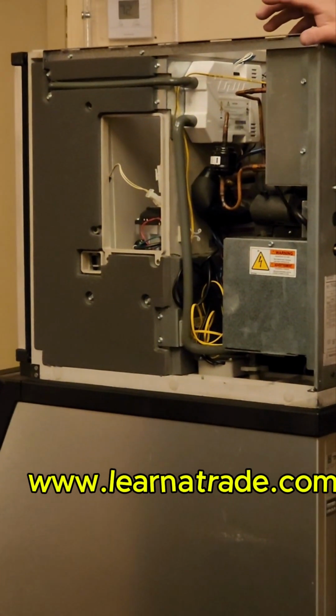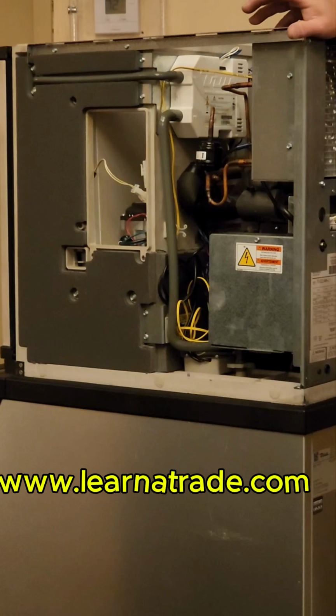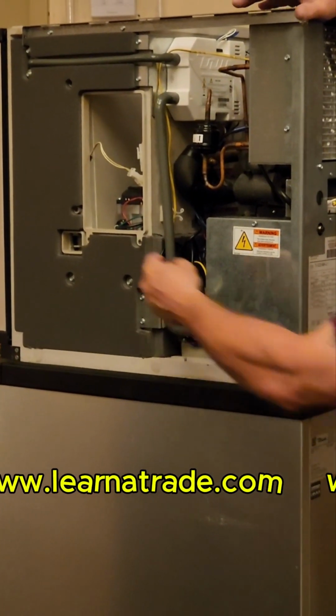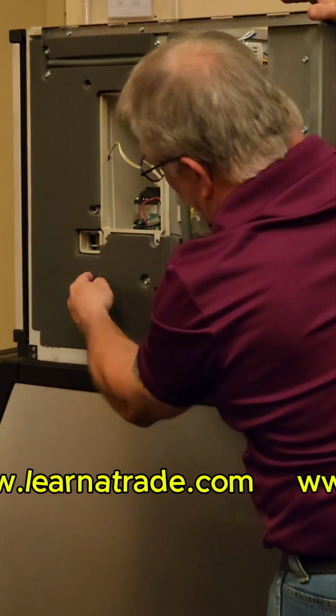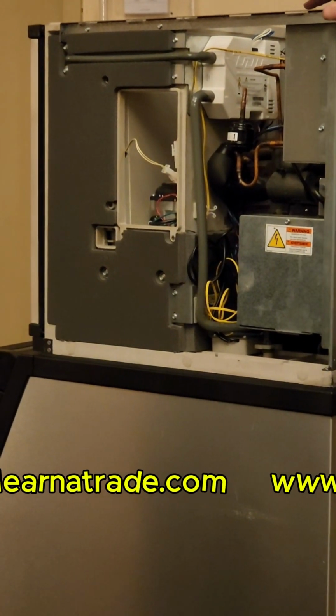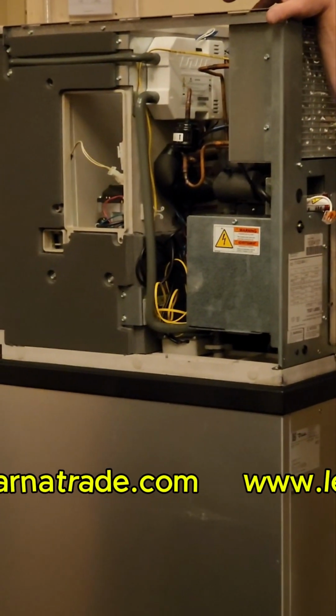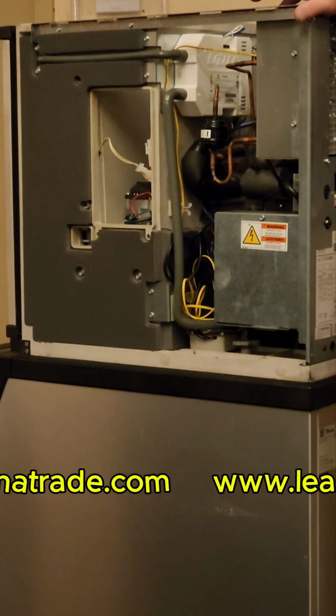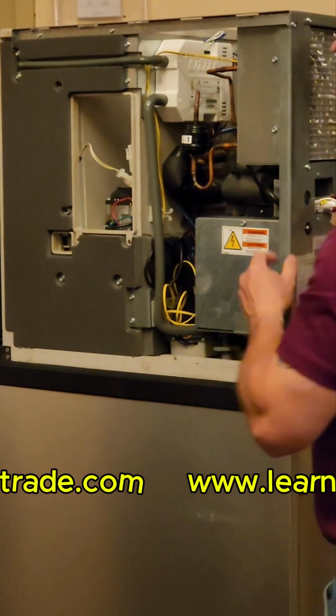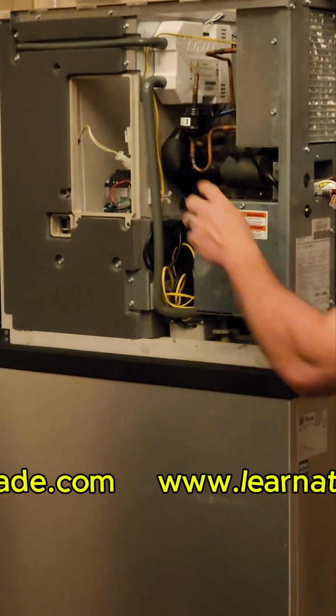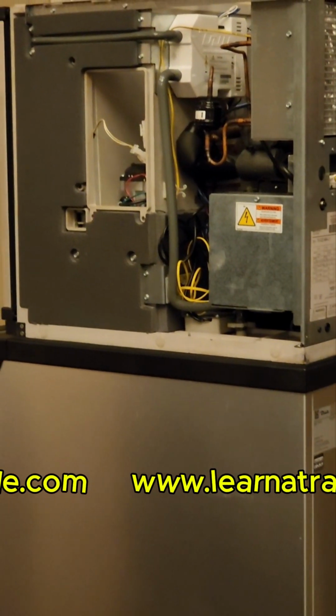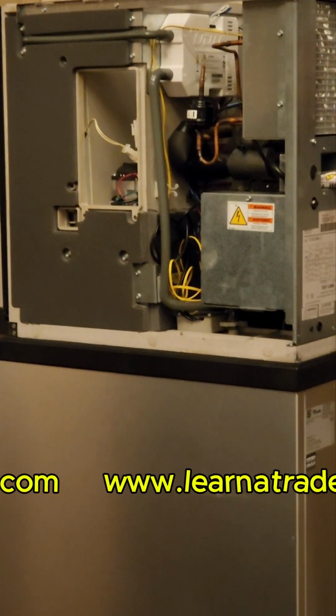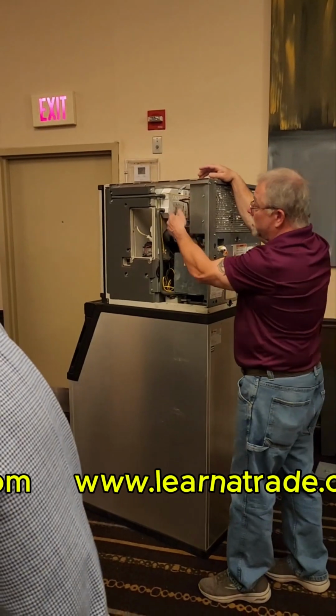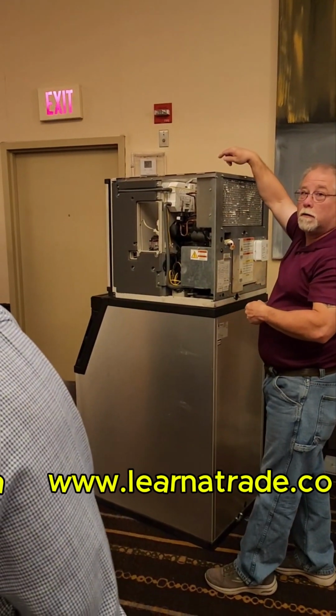Do you have a question? Yeah, if it comes down to it, is it possible to change the evaporator? Well, come on, oh golly, yeah. One, two, three screws on that side, three screws on the other side. Pierce the valve into your refrigerant line, dump the charge, cut it out—I'll show you on the other side. Cut out your liquid line dryer, and of course anytime you open the system, change your liquid line dryer. But it's 3 screws, dump the charge, cut—there's 4 cuts.